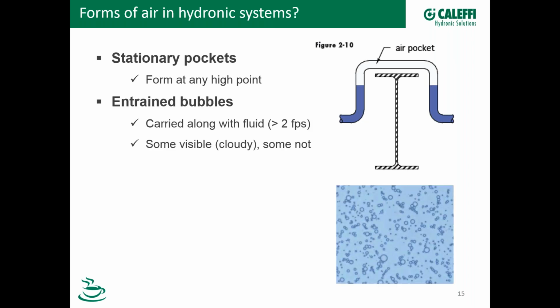The other form of air is entrained bubbles. So entrained bubbles, like this picture shows here, can be carried along with the fluid. And as long as you have more than 2 feet per second, then those air bubbles will be carried along. Now, some of these are visible, like cloudy water. Like if you take a glass of water out of a faucet that has an aerator on there, you can see that cloudy look, and those are entrained air bubbles. And the really small ones, sometimes you can't even see those.